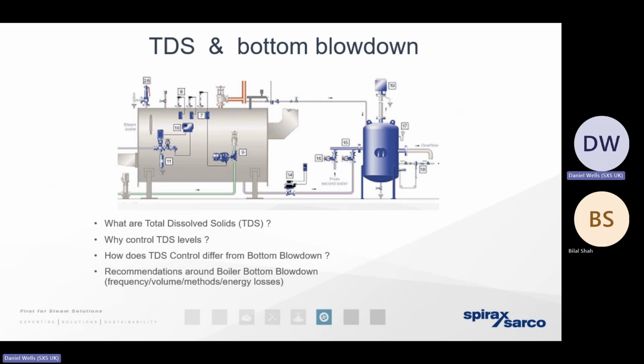So we perform what we call bottom blowdown. Bottom blowdown is performed by, we crack open a little valve, and the water that's within the boiler at 10 bar gauge, 184 degrees, as it falls in pressure, moving across that valve, it's going to perform a very, very violent blast action. And that means that a lot of the sediment that sits at the bottom of the boiler is going to be blasted away. We need to take it to waste.